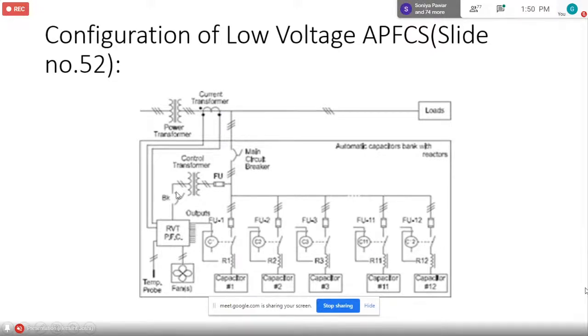Actually, you don't need the voltage transformer. You can straight away connect the fuse, the power factor controller. Through the fuse, you can connect to the live conductor. You need only one, so you can connect to the R phase or Y phase or B phase. So this is phase-to-phase supply. It will sense phase-to-phase and then current, because it's sensing the voltage.